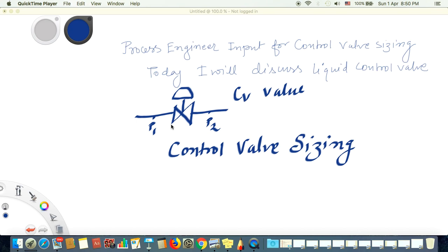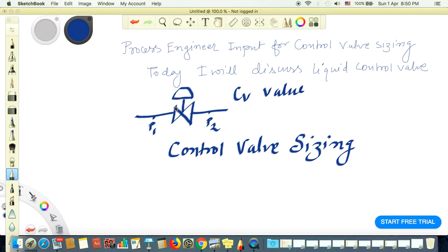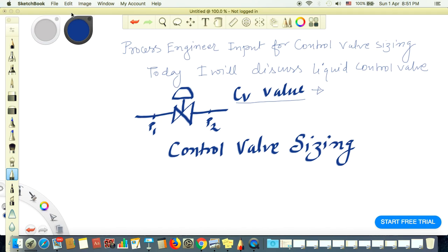Hello friends, today we will discuss what process engineers do, or what kind of calculations a process engineer performs for control valve sizing. We depict the control valve like this. We consider the upstream pressure of this control valve as P1 and the downstream pressure as P2. Control valve sizing means we want to calculate the CV value of a control valve, because the CV value is the characteristic of a control valve — it tells how much pressure drop it will take for different flows and how much flow rate will pass through it.